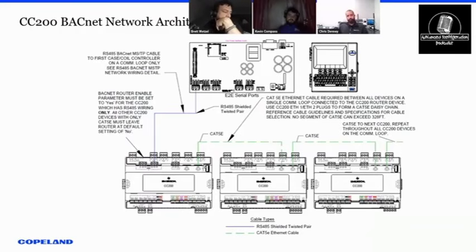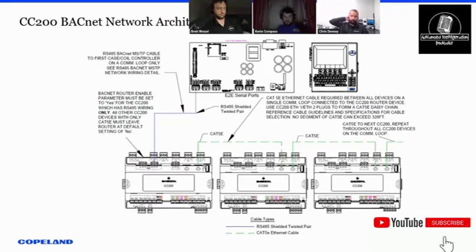So is that just every single circuit is RS-485 then Ethernet, or is it just one case gets the RS-485 signal and then everything else is BACnet over IP? We like it to be one case with RS-485 and then everything else, as many as up to 32 additional modules on that with BACnet IP. Does the E3 support BACnet IP? Yeah. Oh, so you can just go straight back to the IP and just get rid of the RS-485 completely? Yeah, and that's a huge reason, I was about to segue into, Kevin, supporting this architecture now really sets us up to be able to use all BACnet IP, all Cat5 with E3.